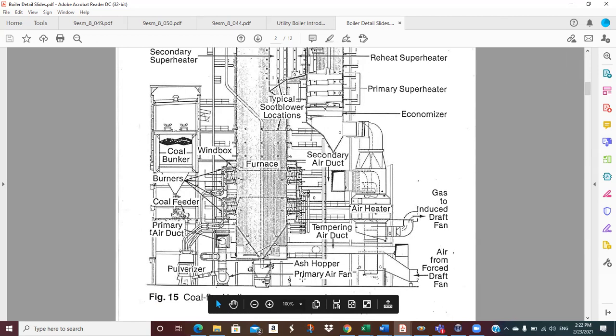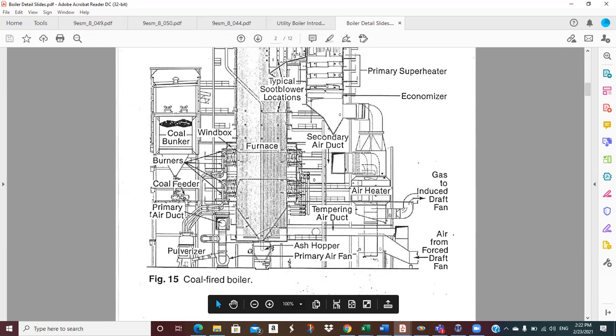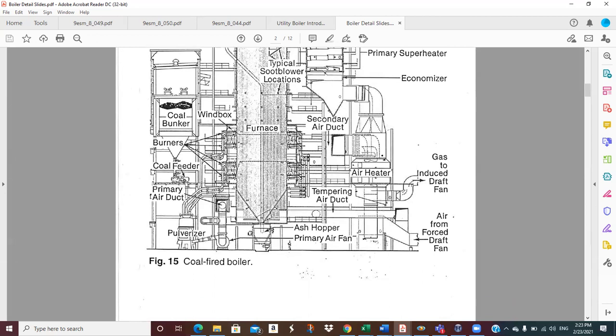induced draft fan. We've got ash hoppers, where some solids fall off the side of the walls, and stuff that falls down here can be taken out the bottom. We usually have a little stream of water down here in the bottom, so when hot stuff falls down from the combustion, it kind of goes psss. If we get to visit, we can open up a door right down here, bend down, and look up and see the bottom of the fireball and all the stuff sticking on the tubes. It's a pretty interesting view.